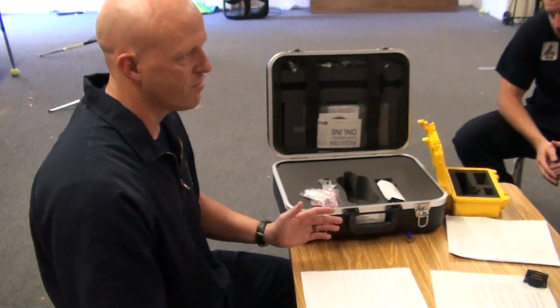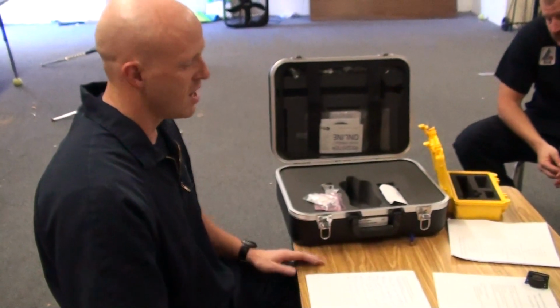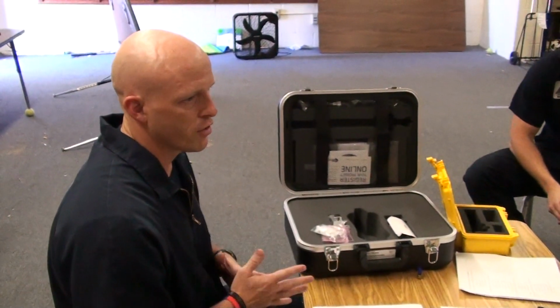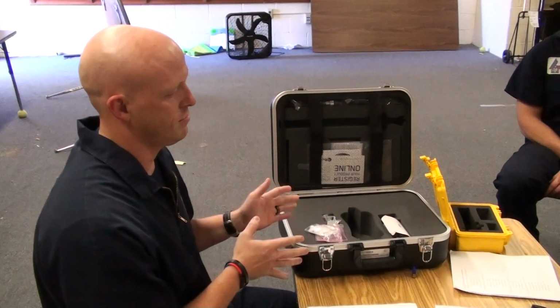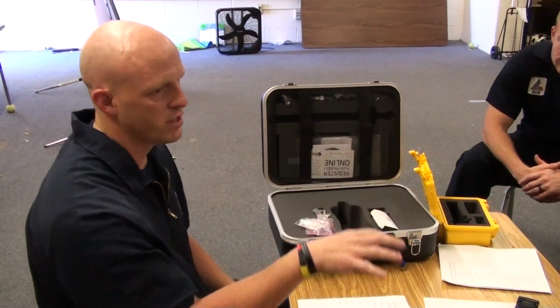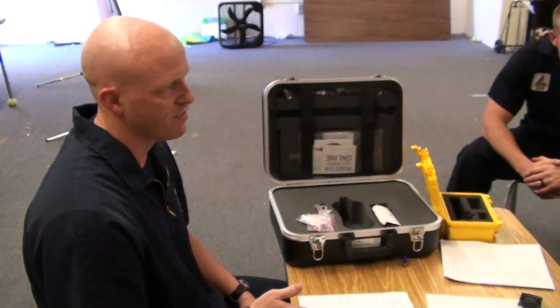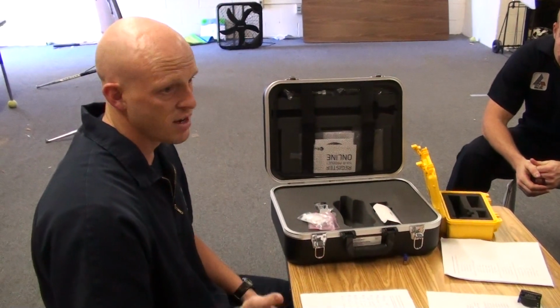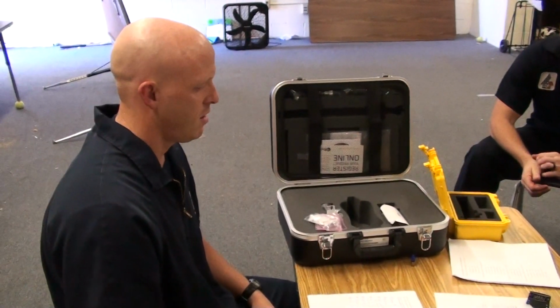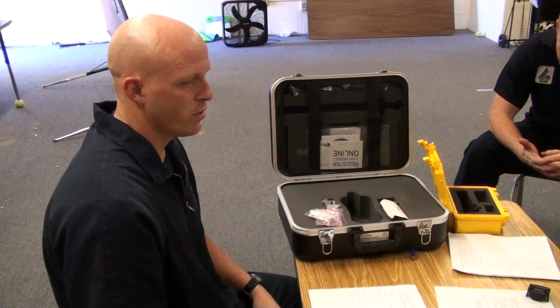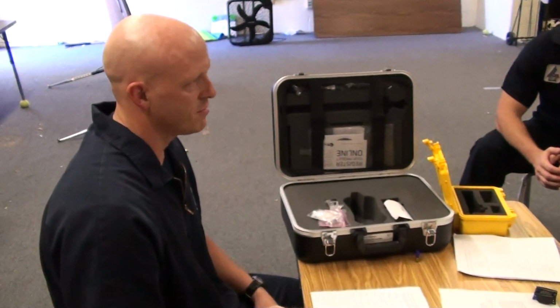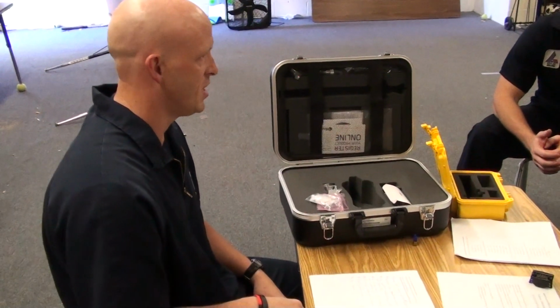It takes roughly 15 minutes. As of now, I've been told they're going to put that on a separate piece of equipment and drive it to each station, so everybody doesn't have to go to station 5 once a month. That could change, but that's the way it is for now. They need to be calibrated once every 3 months, same process, they just hit calibrate instead of bump test.